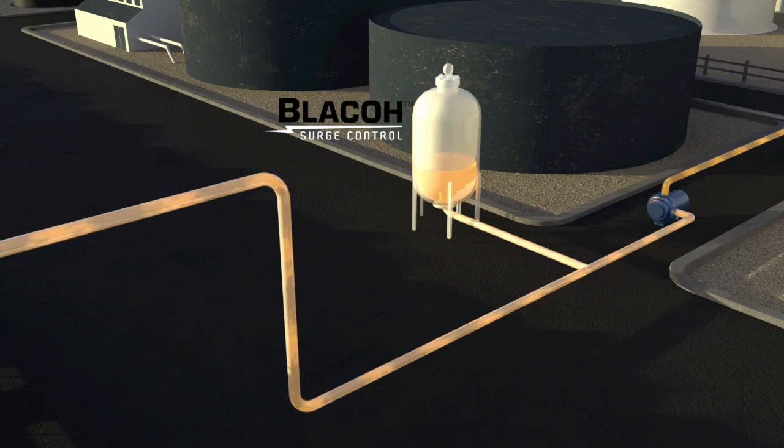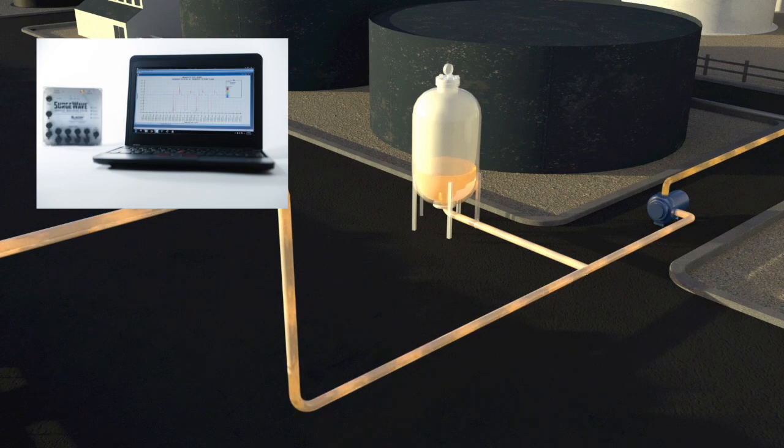Because transient pressure waves are moving near the speed of sound, monitoring surge pressures requires a high-frequency pressure detection device, also known as transient monitoring.